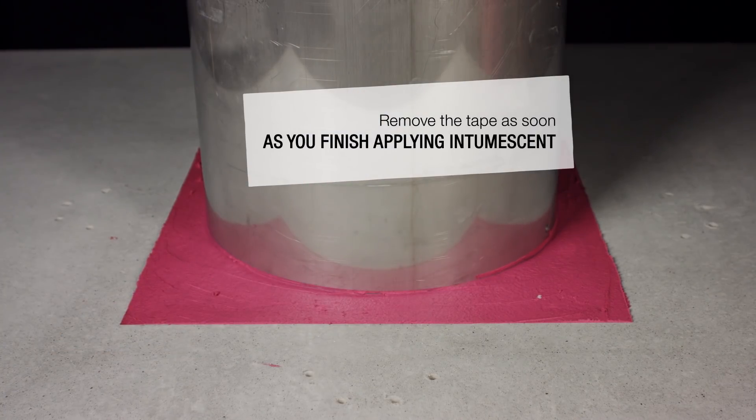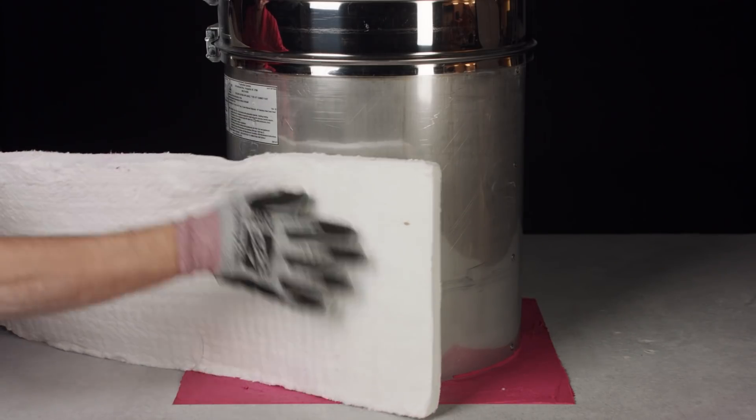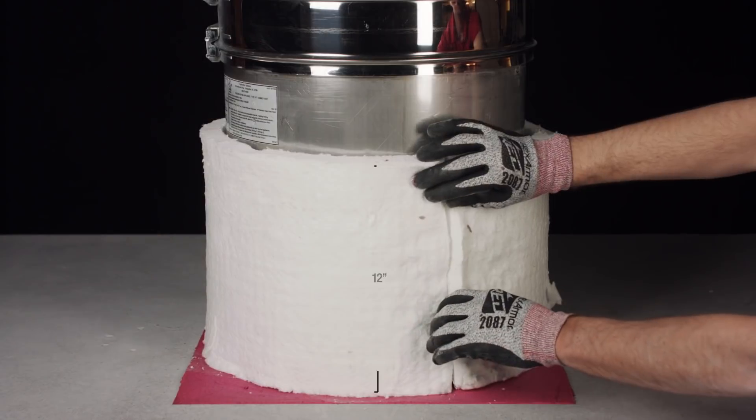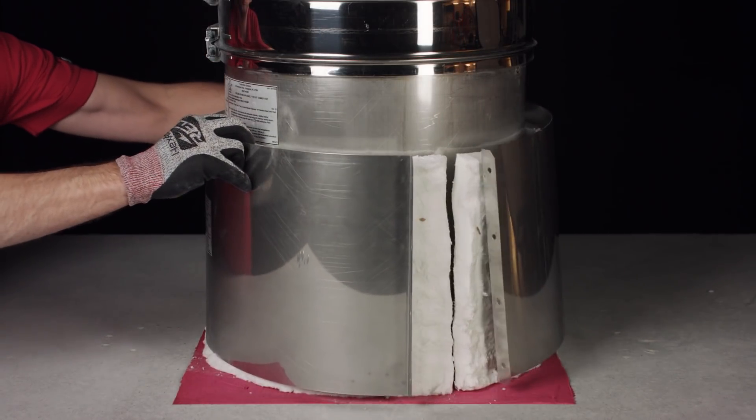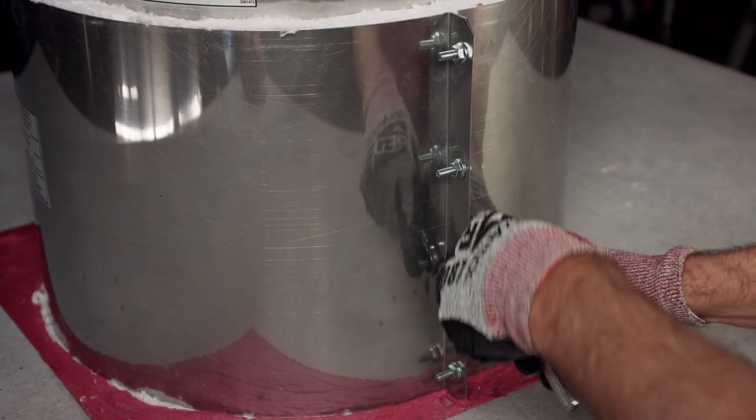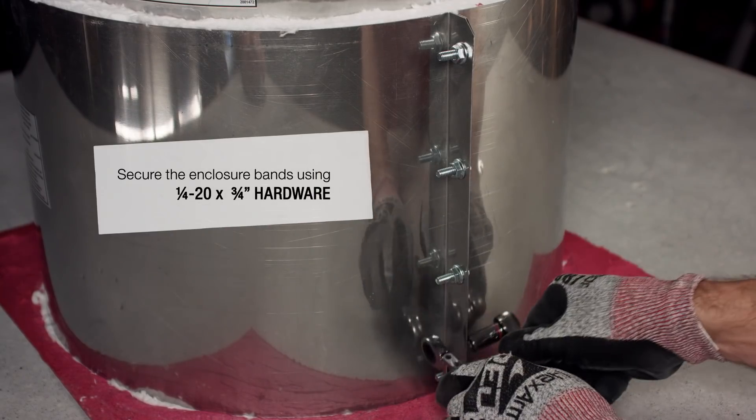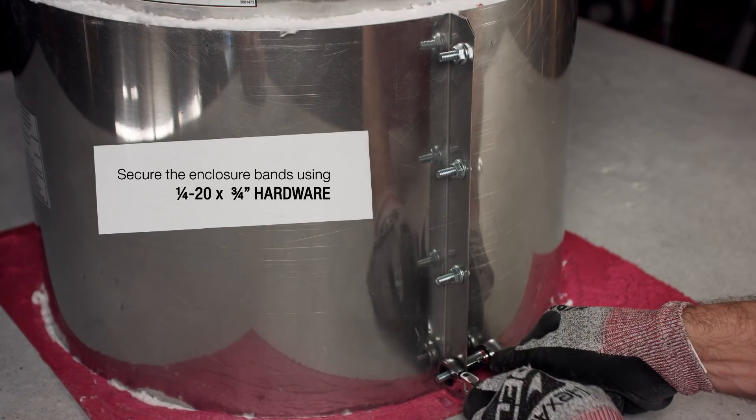Allow the intumescent to dry enough to create a skim coat. Then wrap one layer of 12 inch wide insulation around the base of the duct and place the half enclosure band around the insulation. Use quarter 20 by three quarters of an inch hardware to fasten the tabs of the half enclosure bands together.